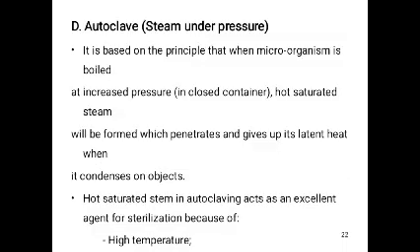D. Autoclave. Steam under pressure is based on the principle that when water is boiled at increased pressure in a closed container, hot saturated steam will be formed, which penetrates and gives up its latent heat when it condenses on objects. Hot saturated steam in autoclaving acts as an excellent agent for sterilization because of its high temperature.